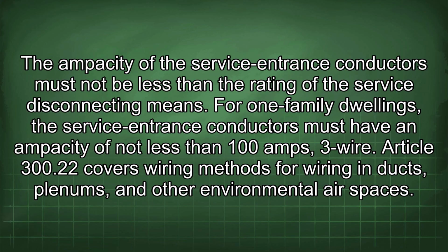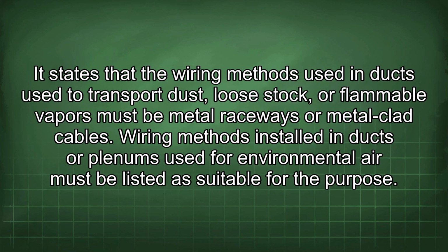Article 300.22 covers wiring methods for wiring in ducts, plenums, and other environmental airspaces. It states that the wiring methods used in ducts used to transport dust, loose stock, or flammable vapors must be metal raceways or metal-clad cables. Wiring methods installed in ducts or plenums used for environmental air must be listed as suitable for the purpose.